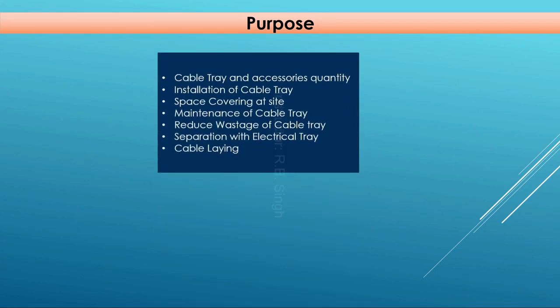The main purpose of the cable tray layout is calculation of cable tray requirements and accessories quantity. Due to this layout, installation of cable tray will be easy at site — understanding where cables go upward, downward, bending at 45 or 90 degrees, or where reducers and expanders are used. All these details you can find in this layout, helping you understand the installation of cable tray.